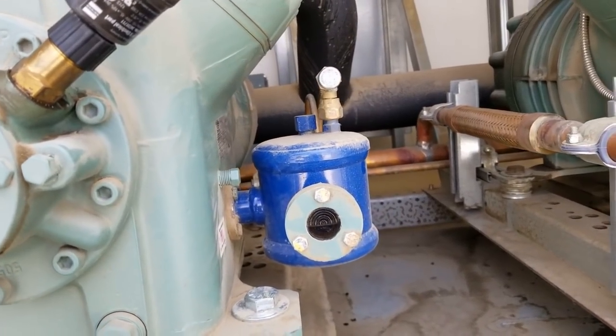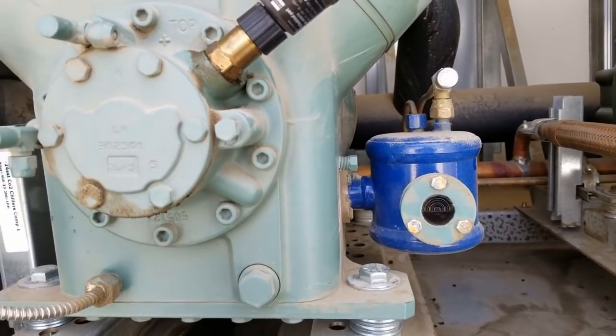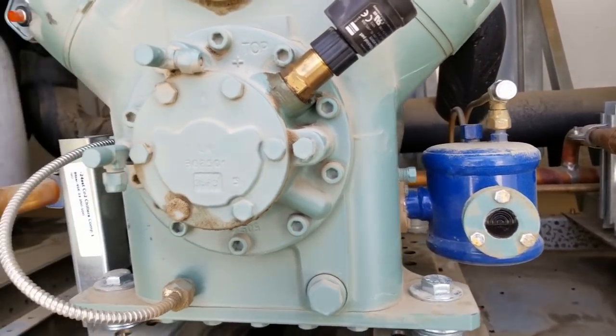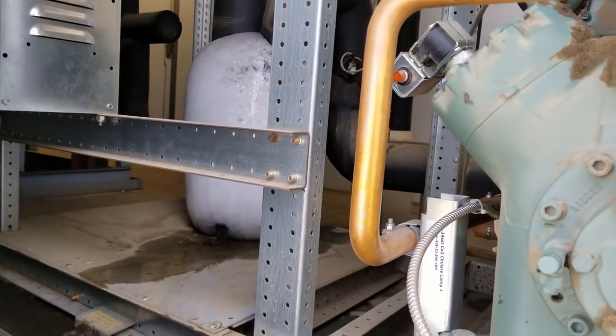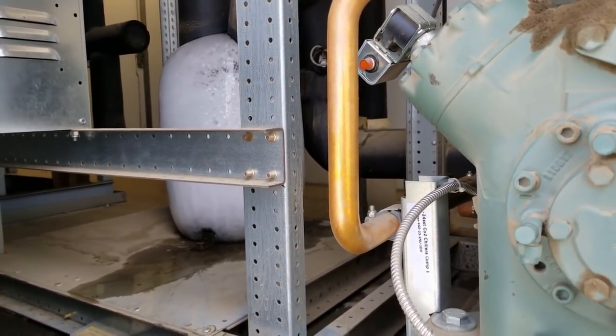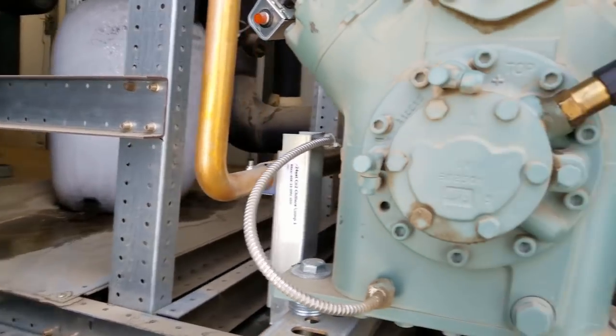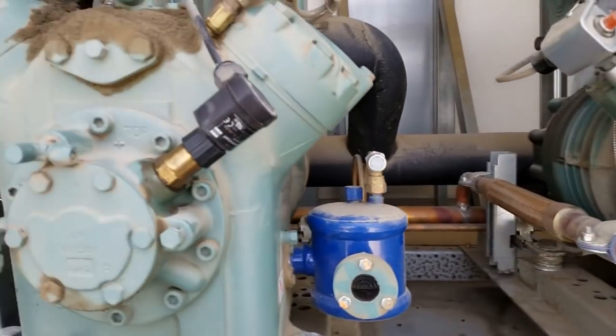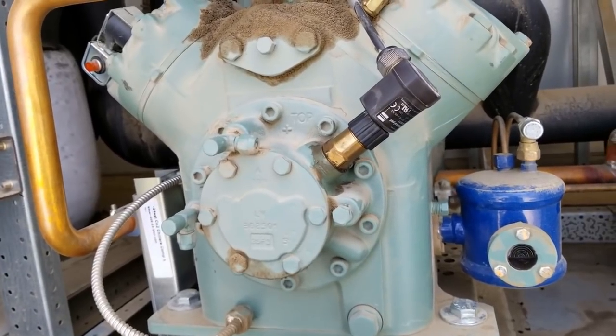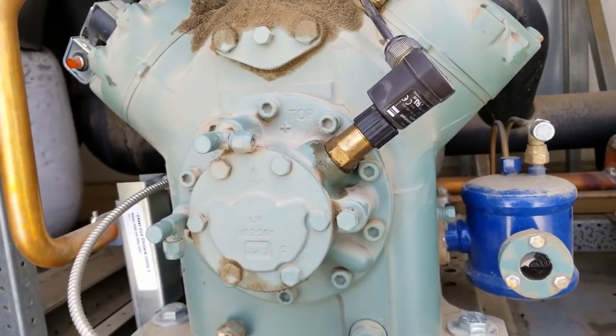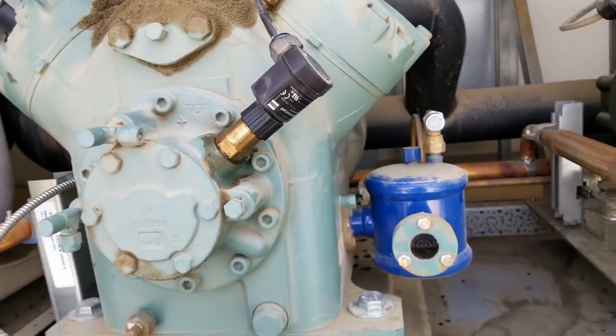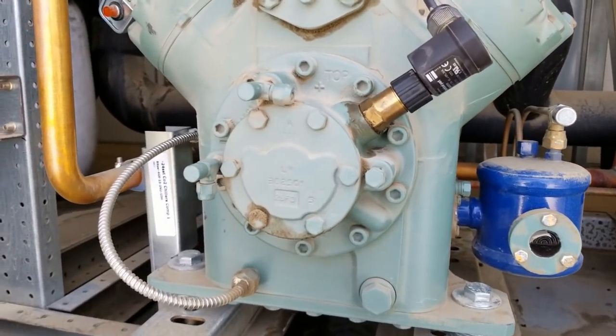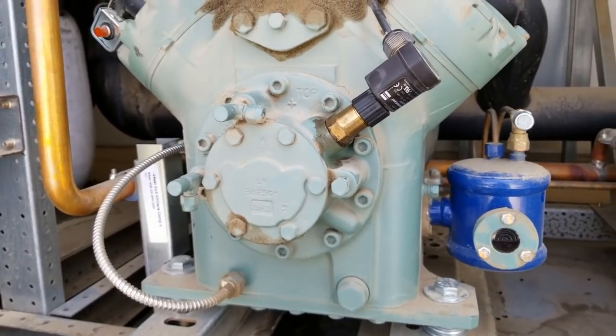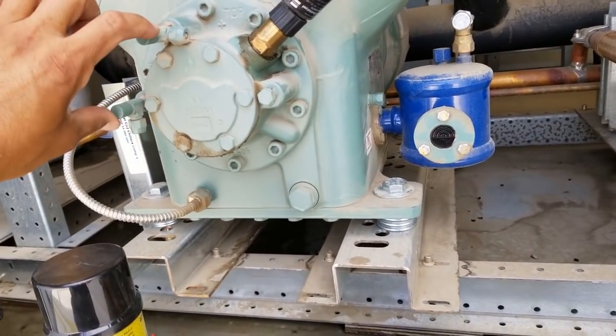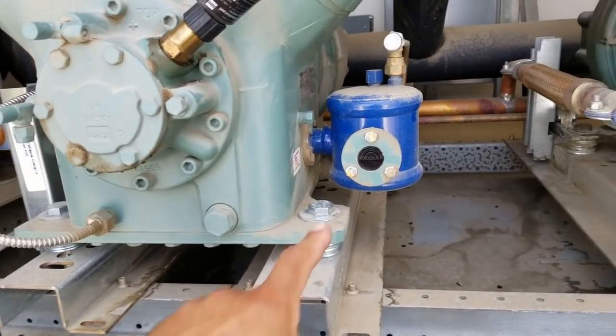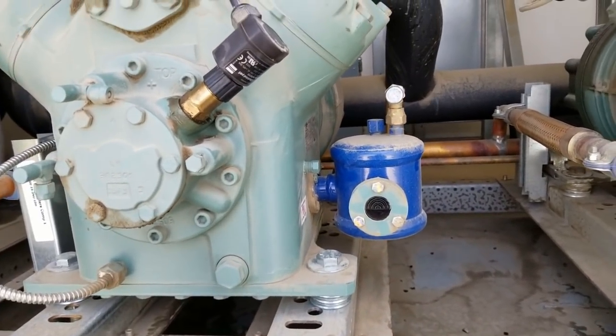I'm going to keep an eye on it. If this happens again, then I'll really dig into it. We'll have to talk to Walmart about adjusting some of their set points so we wouldn't get any flood back to these compressors, because it's just too much. If this is an ongoing issue, versus just once or twice in a long period of time, normally they won't really do anything about it - we'll just come out here, reset a compressor, and move on. Unfortunately, that's the way it goes sometimes. But now we know what's going on with this, how to take my differential. My oil level's good, and we're all set to go.